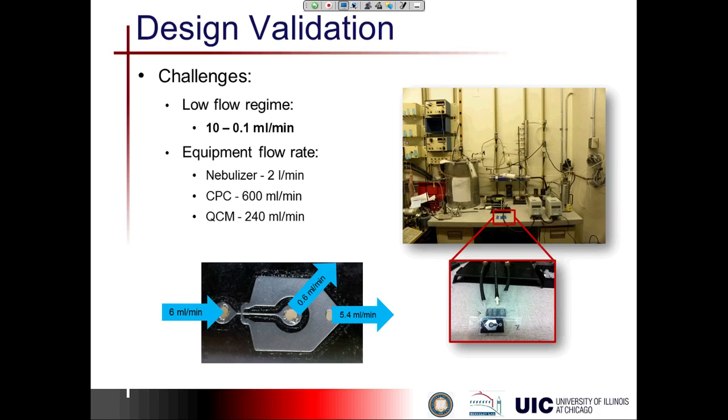The minor flow, if it's a 90%, 10% ratio, right? The minor flow is only 0.6 milliliters per minute, okay? Controlling that flow is very difficult, but actually taking particles from that flow and then putting them into some of these devices to detect how many particles are getting through is almost impossible, okay? So it's very difficult. This is one of the challenges that we have.